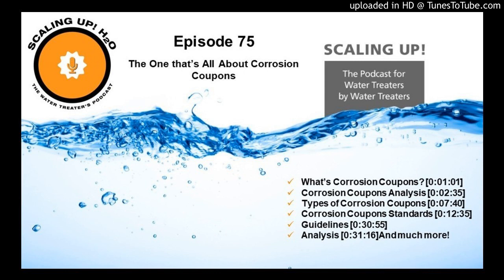Another question I get quite a bit is how long should I keep corrosion coupons in the system? Folks, this is really up to you. You can keep them in as long or as short as you want, but you need to realize this: the longer the corrosion coupons are in the system, the more they are going to mimic the system.